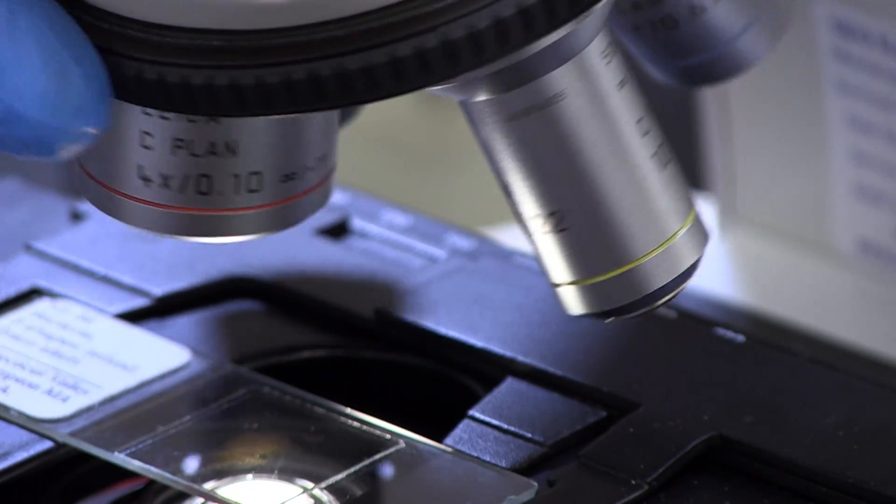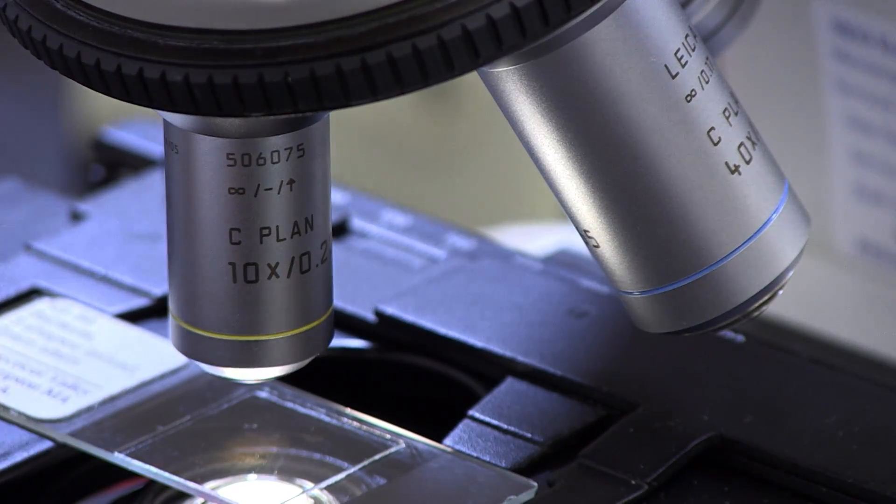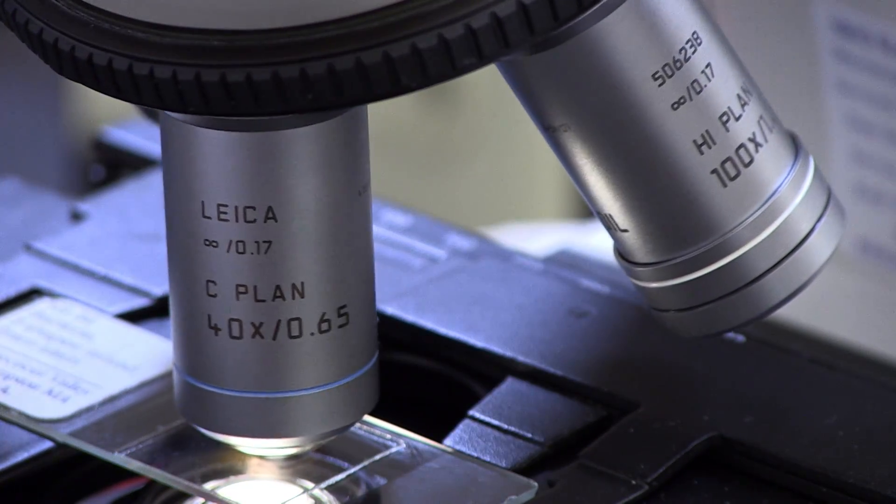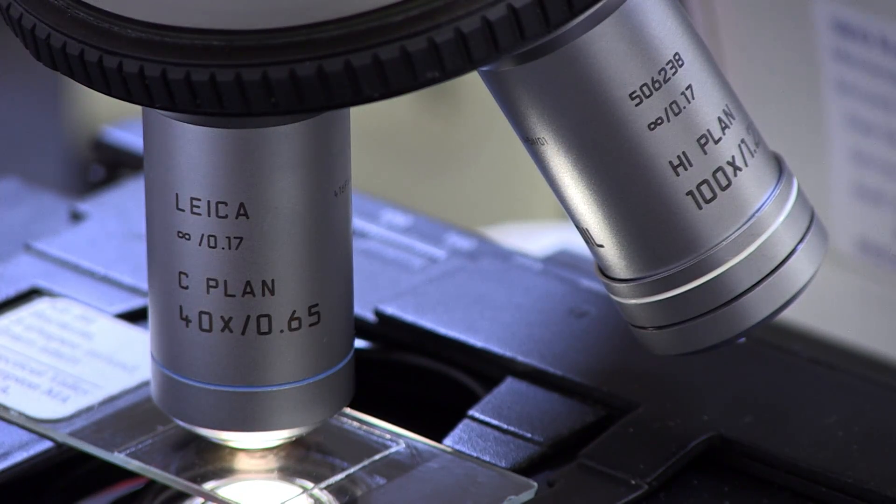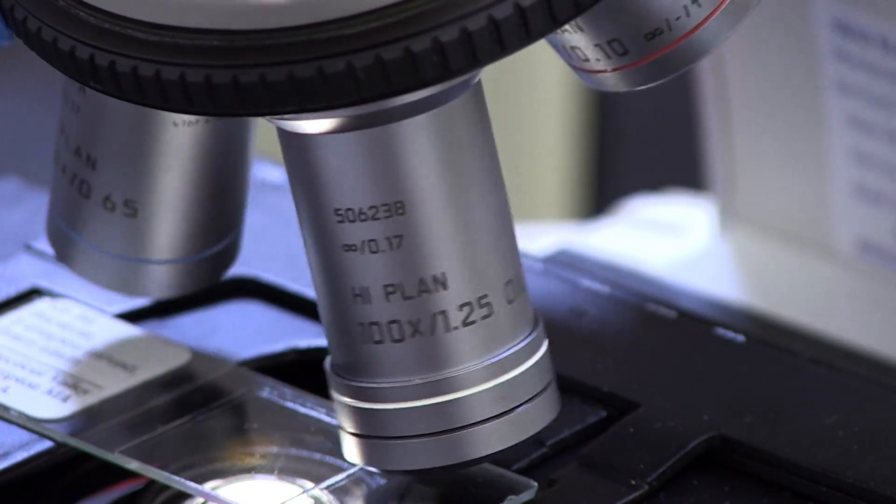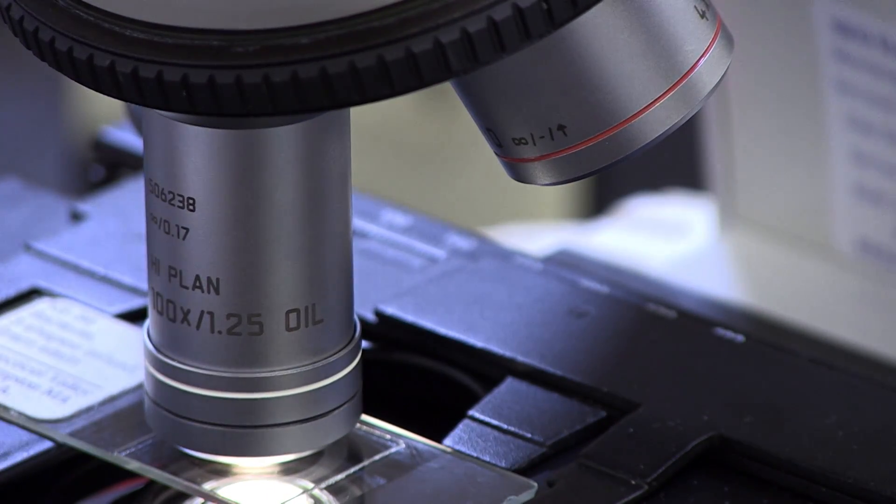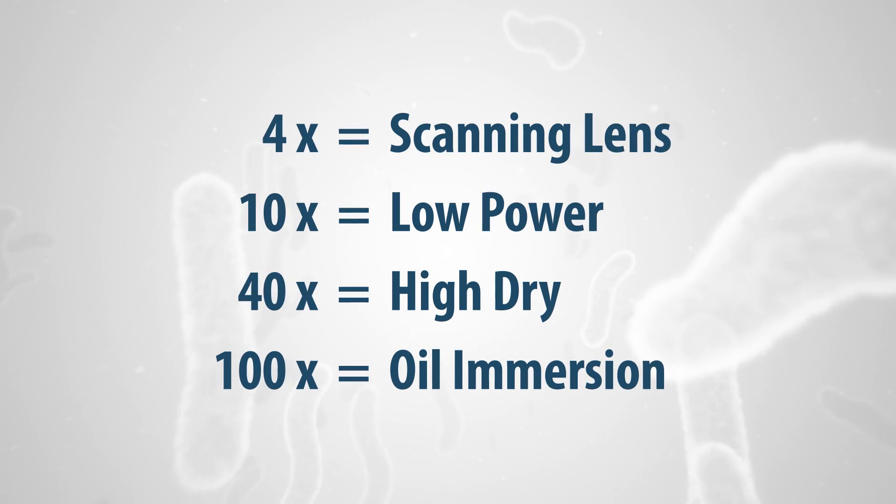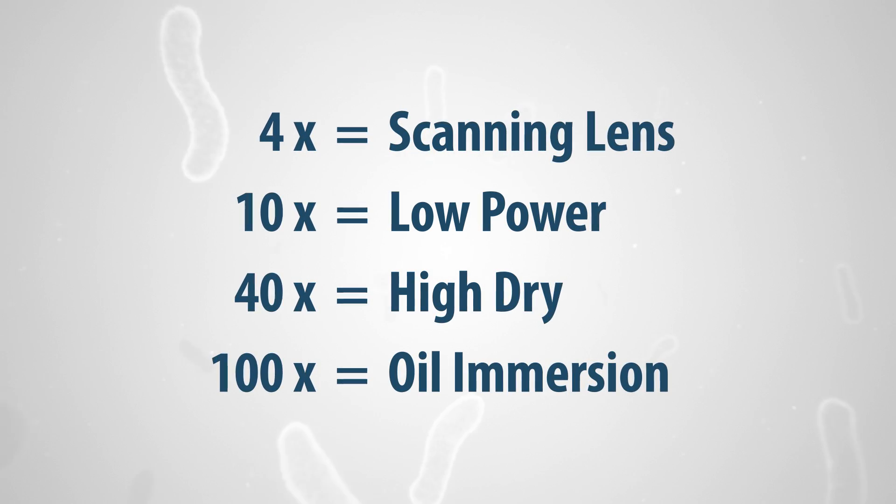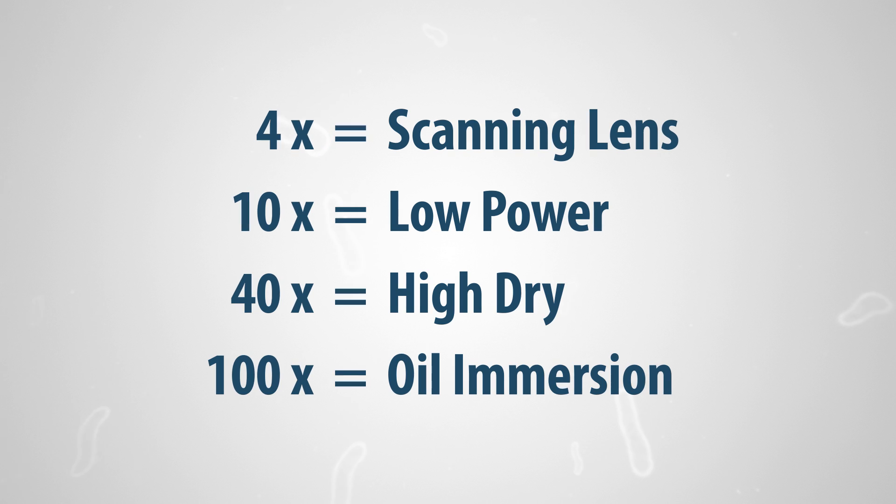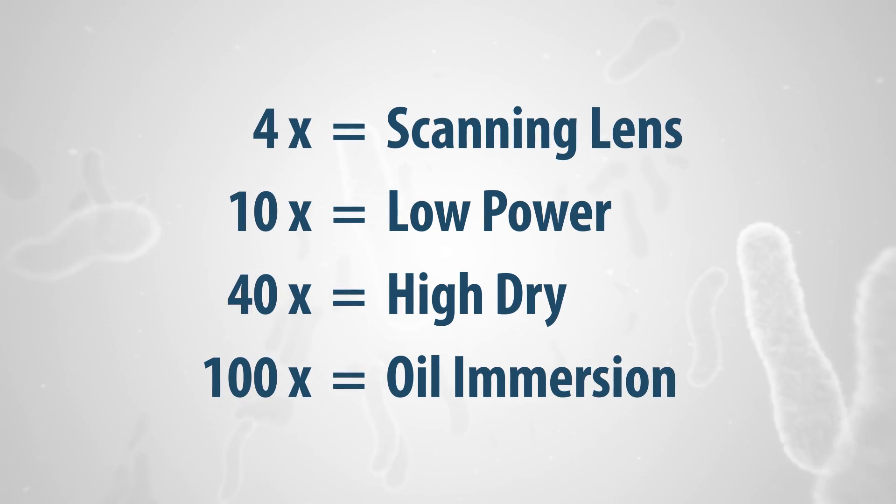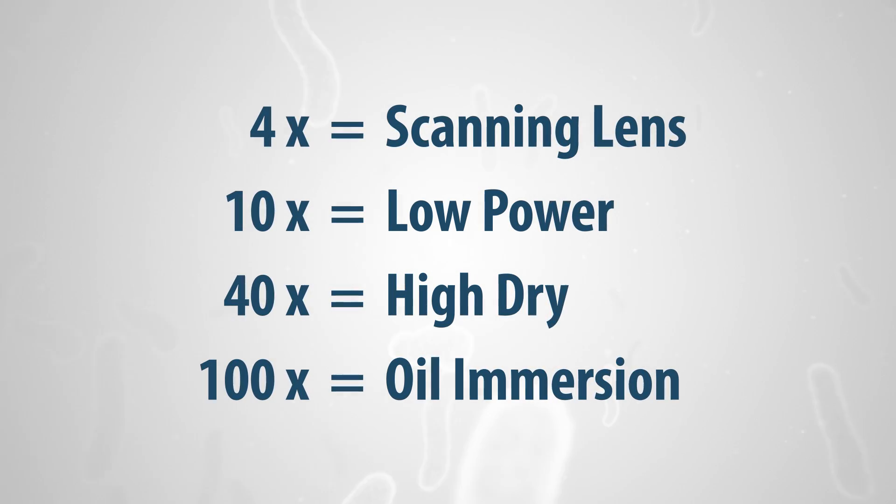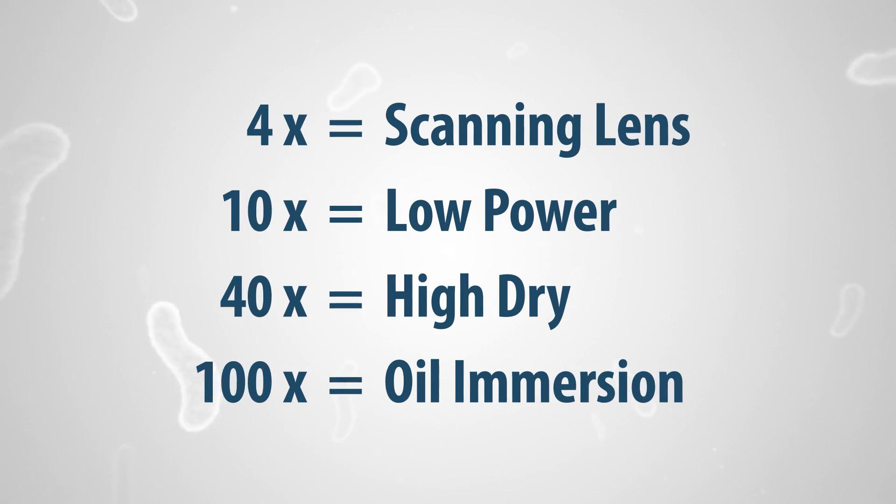Objective lenses, the second lens system of the light microscope, are found just above the stage. The three or four objectives are attached to a revolving nose piece that allows the lenses to be rotated into position. The four objectives have magnifications of 4x, 10x, 40x, and 100x, designated as scanning lens, low power, high power, and oil immersion, respectively.